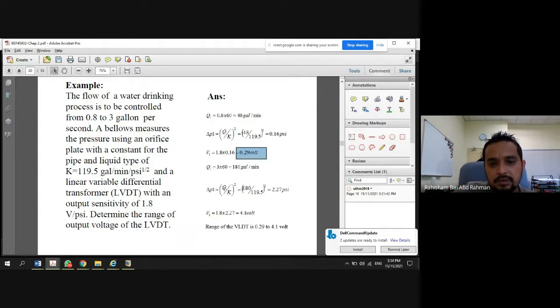Okay, now we know that the flow for the second section is 3 gallon per second. Now we calculate the value for 3 gallon per second, and we perform similar calculations, and that will give us V1, or this one V2. We say V2 1.8 because it says 1.8 is the sensitivity, and we know the pressure difference in section 2 is actually 2.27. So we multiply the value of the sensitivity, and that will give us actually 4 volt.